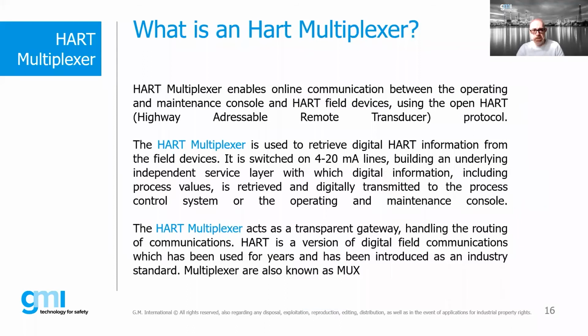The HART multiplexer is a device that is used to connect HART field devices to an asset management system. The HART multiplexer enables online communication between the operating and maintenance console and HART field devices using the open HART protocol. The HART multiplexer acts as a gateway, routing communication between the maintenance PC workstation and HART field devices. It queries each HART device, retrieves the information, and stores it in an internal database. This information is available for the device management tool, for example, PACTware.